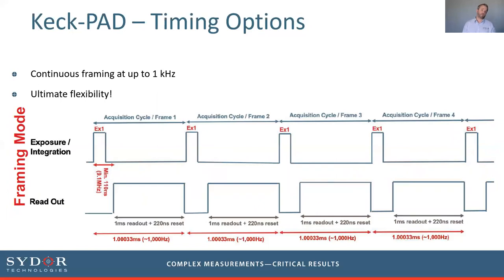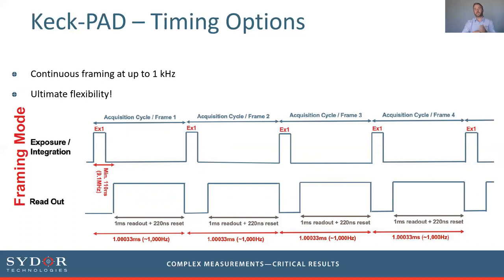The other configuration is to set the device up to continuously stream data using just one frame or one exposure. We can read out immediately after that exposure and set it up to continually frame and take measurements, as you might do in simple non-time-resolved diffraction experiments. This can still be done at reasonably fast rates, up to about a kilohertz.